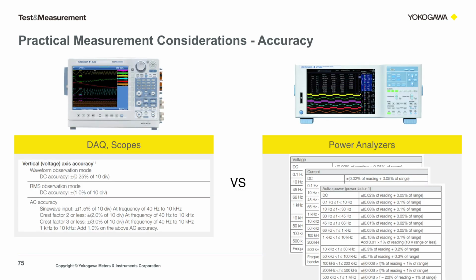The main difference between these two instruments is the level of detail provided in their specifications. Power analyzers specify accuracy on voltage, current, and power from DC to the full bandwidth of the instrument. Our DAQ and oscilloscopes will generally spec usually at DC, and sometimes that's going to be typical and not guaranteed.